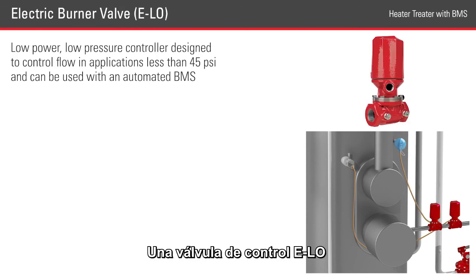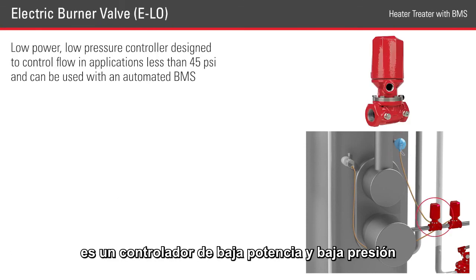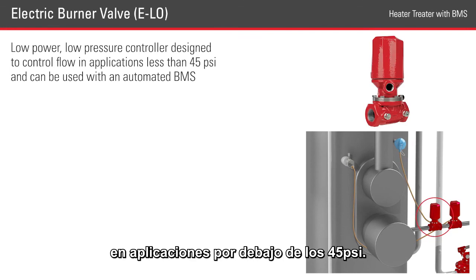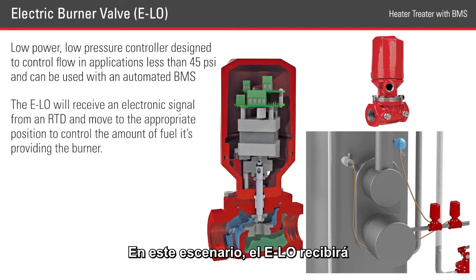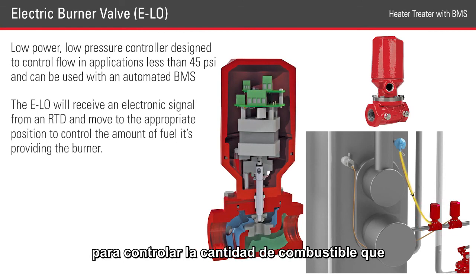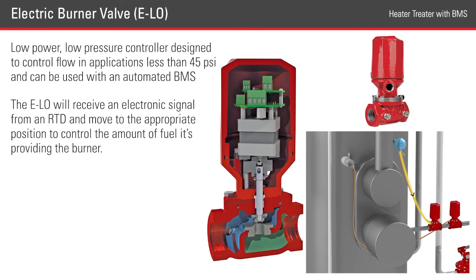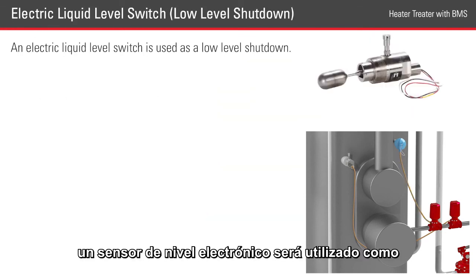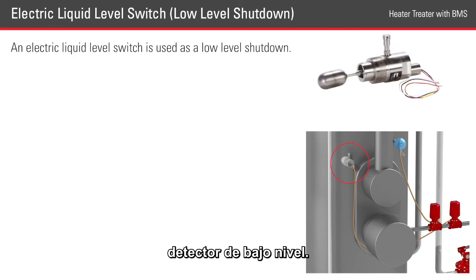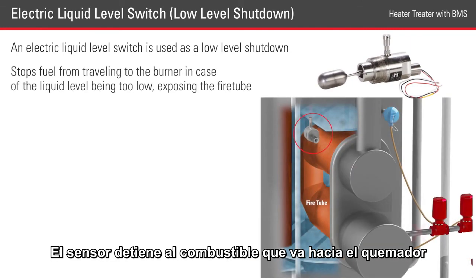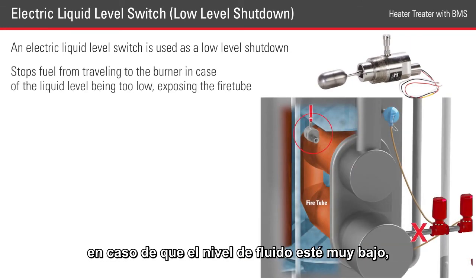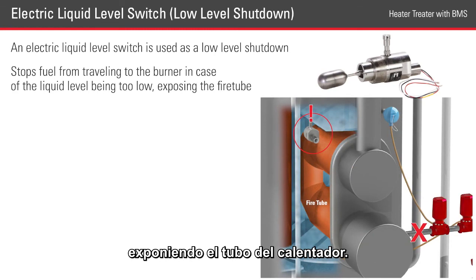The ELO control valve is a dynamic, low-power, low-pressure controller designed to control the flow in applications less than 45 psi and can be used with an automated BMS. In this scenario, the ELO will receive an electronic signal from the RTD and move to the appropriate position to control the amount of fuel it's providing to the burner. In an automated BMS, an electric level switch will be used as a low-level shutdown. The switch stops the fuel from traveling to the burner in case of the liquid level being too low, exposing the fire tube.